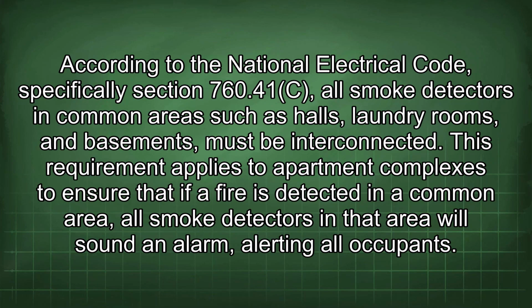According to the National Electrical Code, specifically Section 760.41c, all smoke detectors in common areas such as halls, laundry rooms, and basements must be interconnected. This requirement applies to apartment complexes to ensure that if a fire is detected in a common area, all smoke detectors in that area will sound an alarm, alerting all occupants.